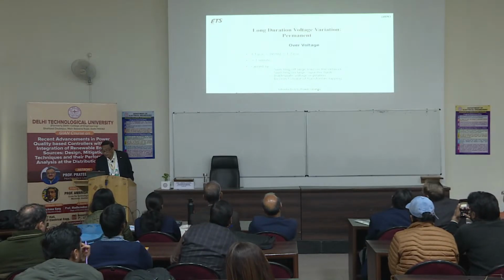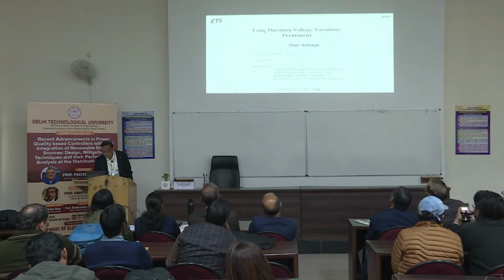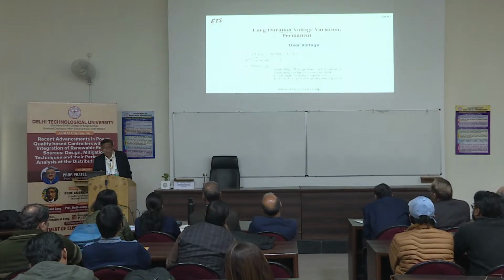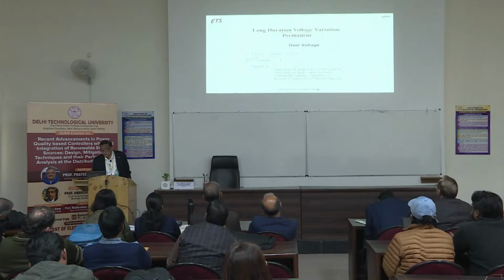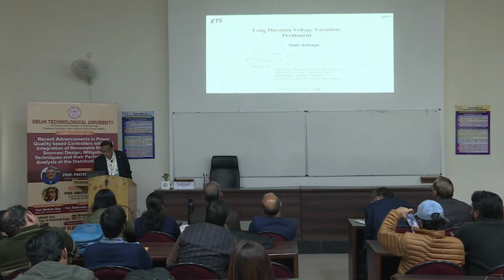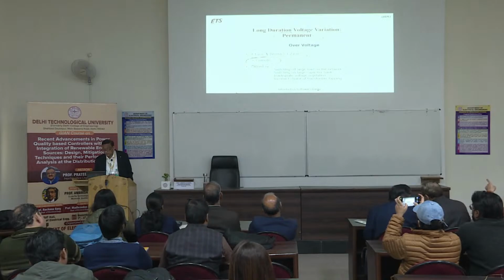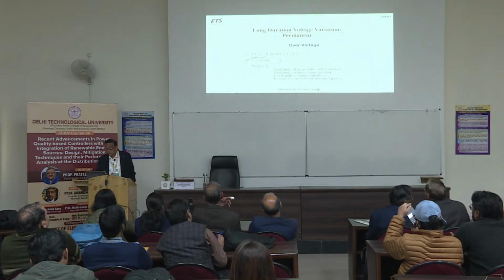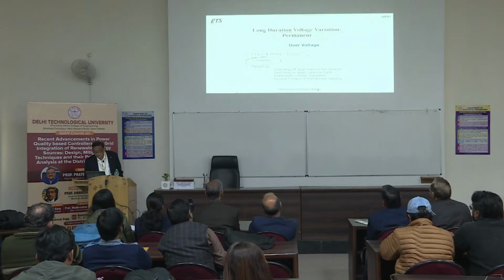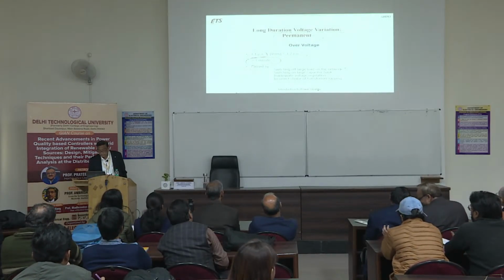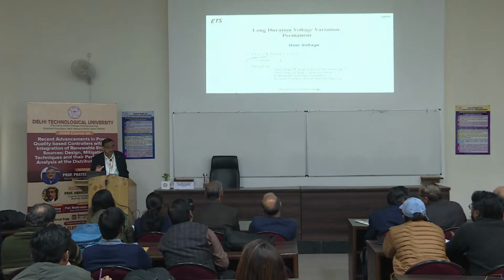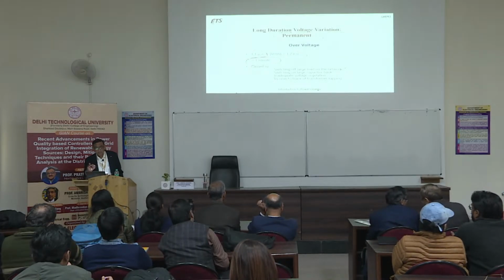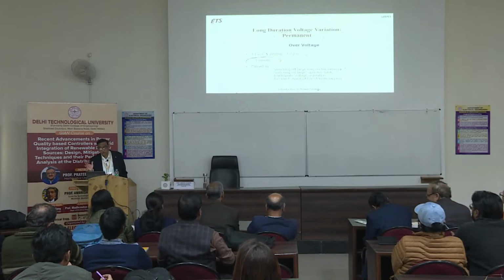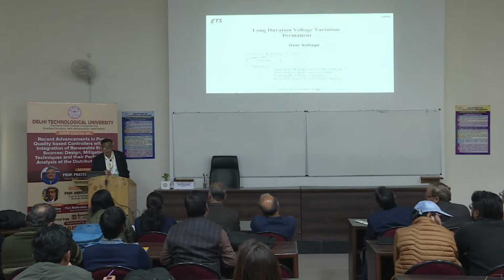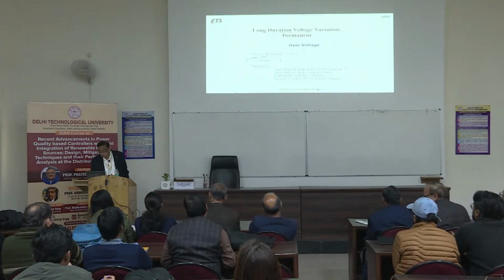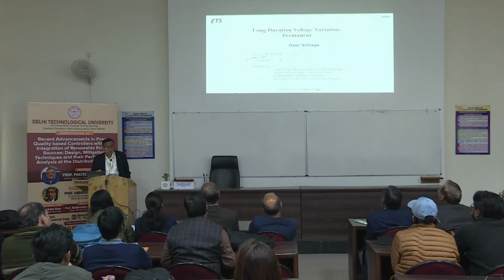Over voltage, permanent, long duration voltage. If it is more than 1 minute, then we call it a permanent, long duration voltage variation, 1.1 pu to 1.2 pu, caused by switching off a large load on the network or switching on a large capacitor bank. Because you have switched on the large capacitor bank, the capacitor bank is supplying the reactive capacitive current, so less current is coming from the source, so less voltage drop, and because of that there is an over voltage for a certain time. Other causes are inadequate voltage regulation and incorrect choice of transformer tappings.